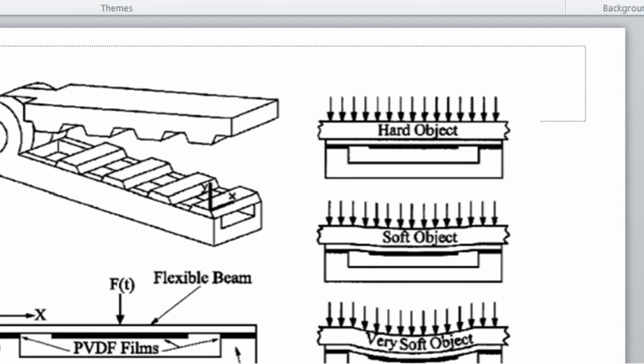To perform faster measurement, a vibrating tactile sensor which makes use of a piezo transducer was developed in research. The transducer, which is made of lead zirconate titanate ceramics, has a resonance frequency as high as 92 kilohertz. When the sensor gets into contact with tissues, its resonance frequency will shift to a new value. The difference between the resonance frequencies under different conditions can then be detected using a vibration detector inside the sensor head.